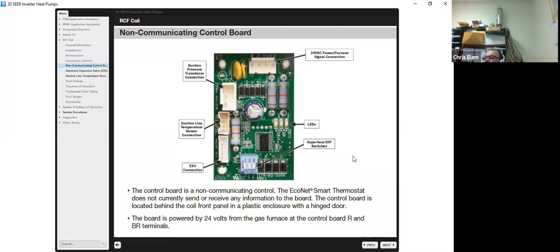So this is a close-up of the non-communicating control board. Right here is the low voltage connections, your R, C, Y1, Y2. They're going to be hardwired right into your control board to the appropriate terminals. Here are your LEDs, because it will actually give you codes as well. You have to take the coil door off, open it up to actually access your coil, your codes. Your suction pressure transducer terminals here, suction line temperature sensor connection, and your EEV.